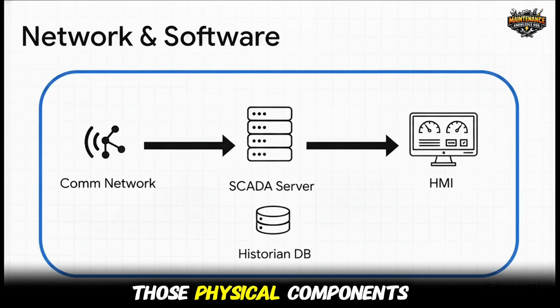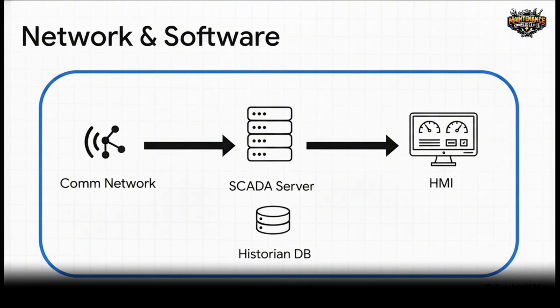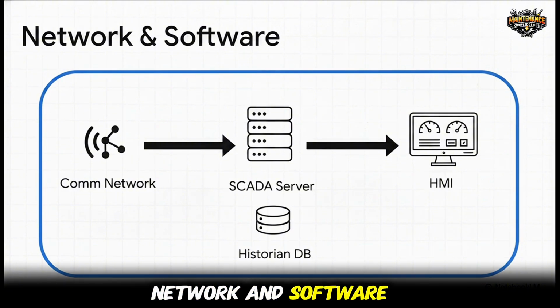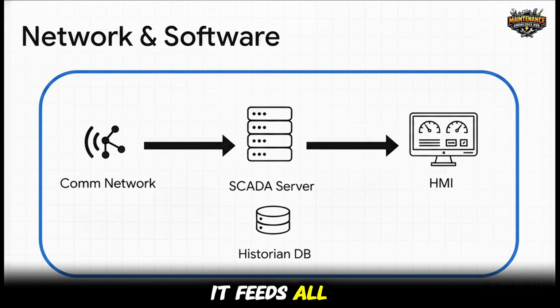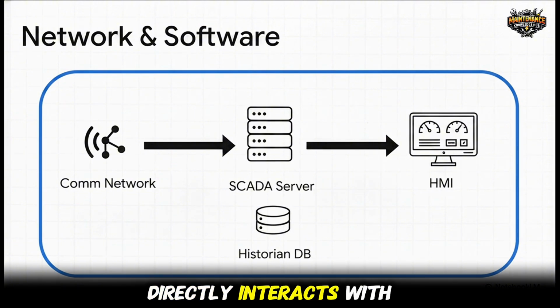But those physical components have to talk to each other. That's where the network and software come in. The communication network, whether that's Ethernet, fiber optics, or cellular, acts as the digital nervous system. It feeds all that data right into the SCADA server, which is the central hub collecting everything. The server then pushes this data to the HMI, or Human-Machine Interface. The HMI is exactly what it sounds like — it's the graphical screen, that visual window where the operator directly interacts with the plant.